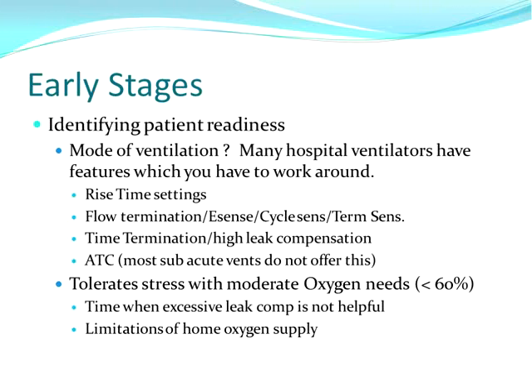So it's easy for us to think through, or hopefully it is, how we would have compensated for volume loss and resistance differences that our newer critical care ventilators do automatically by zeroing to the tubing. Just remembering this, and that the patient isn't getting quote-unquote worse because you might have to increase, particularly in volume ventilation, your volume settings, will really go a long way in making everyone comfortable with that transition.